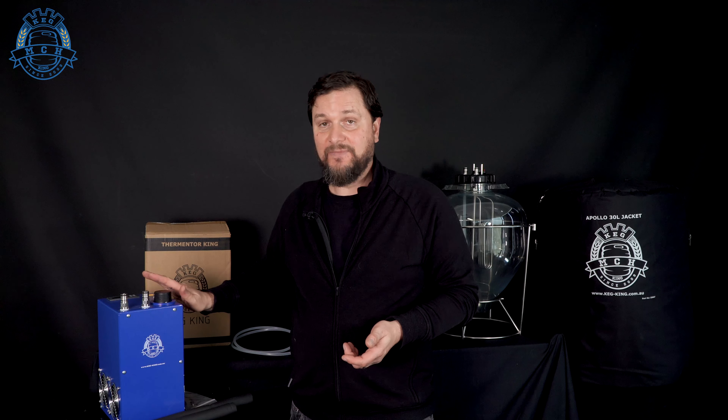The next step for using the Thermentor King is to hook it up and start powering it up so we can prime the pump. It's best when operating these machines that they're close to whatever you're trying to temperature control. To make the pump priming easier, you can pick the machine up and tip it so that the liquid starts flowing through it. We're also going to mix up the liquid — this only takes between 250 and 300 mils of liquid. I'm going to use 200 milliliters of water and 50 mils of glycol.